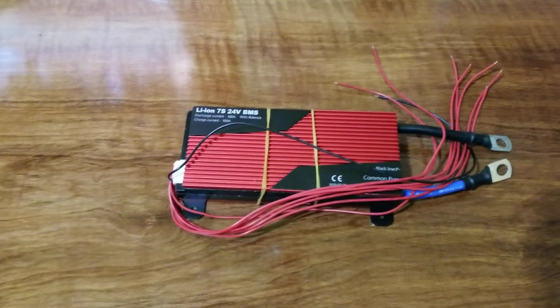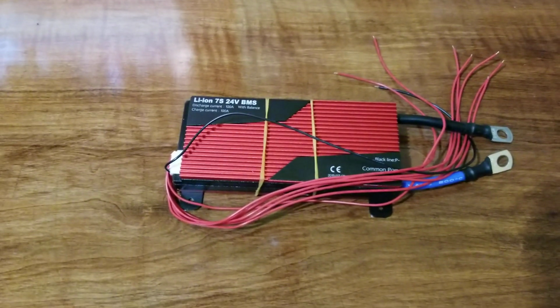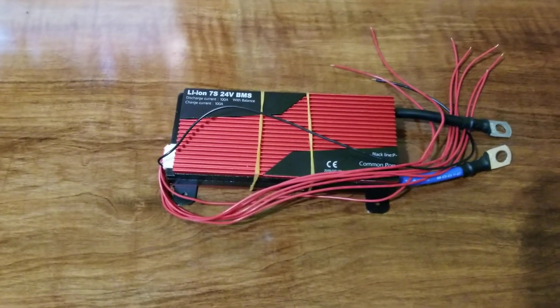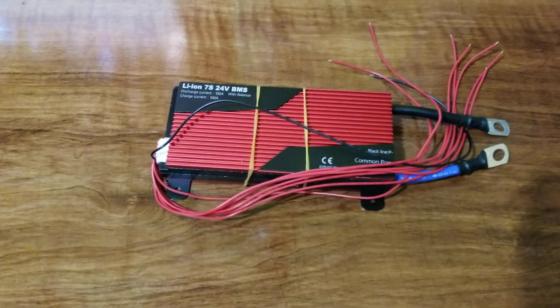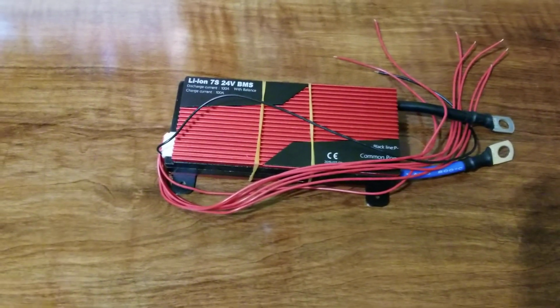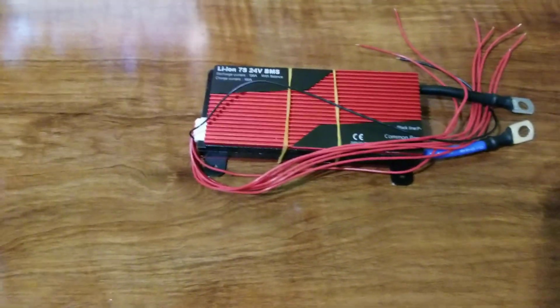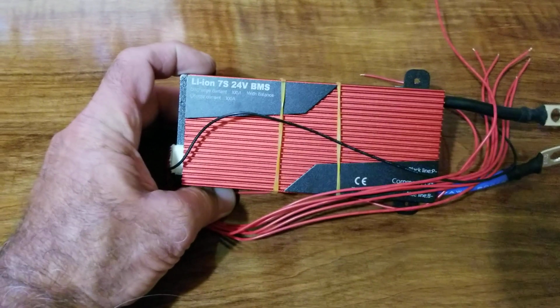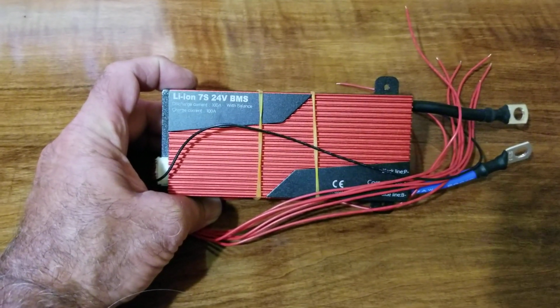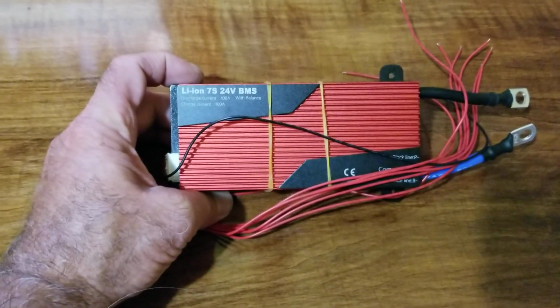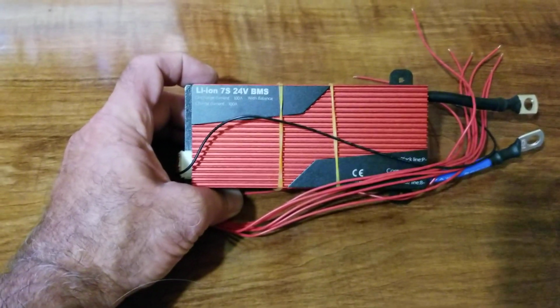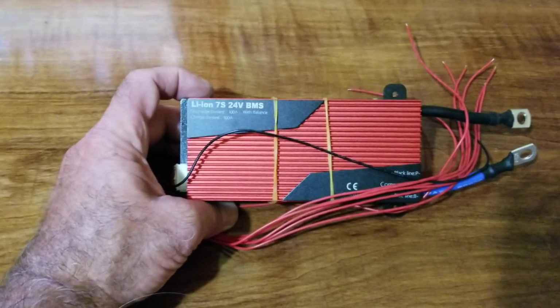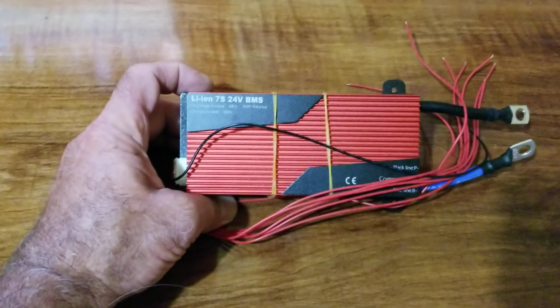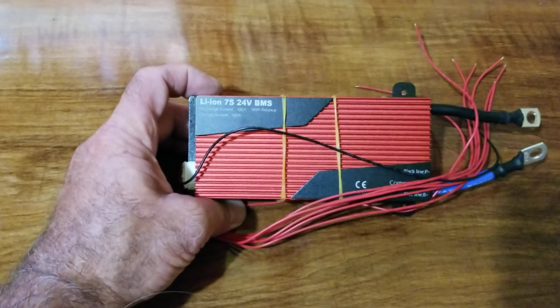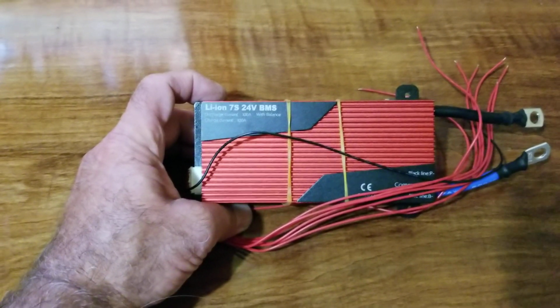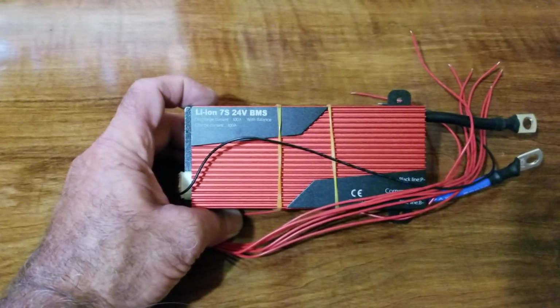In this case it was a TriStar PWM that failed, and I still have it. Its diversion mode is completely defunct. I don't know if that would happen on the solar side, but equipment can fail, and if it fails on the high side and overcharges your batteries, your solar charge controller can turn your lithium ion battery bank into a giant bomb. We don't want that. So rather than relying on the solar charge controllers alone, a true BMS, battery management system, power handling BMS for each battery seems to me the safest thing I can do.